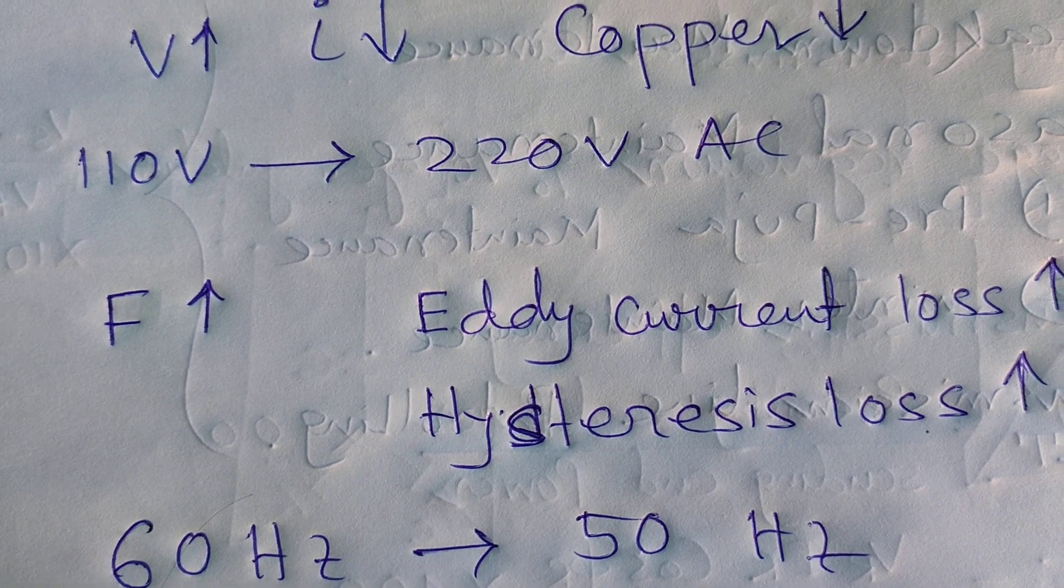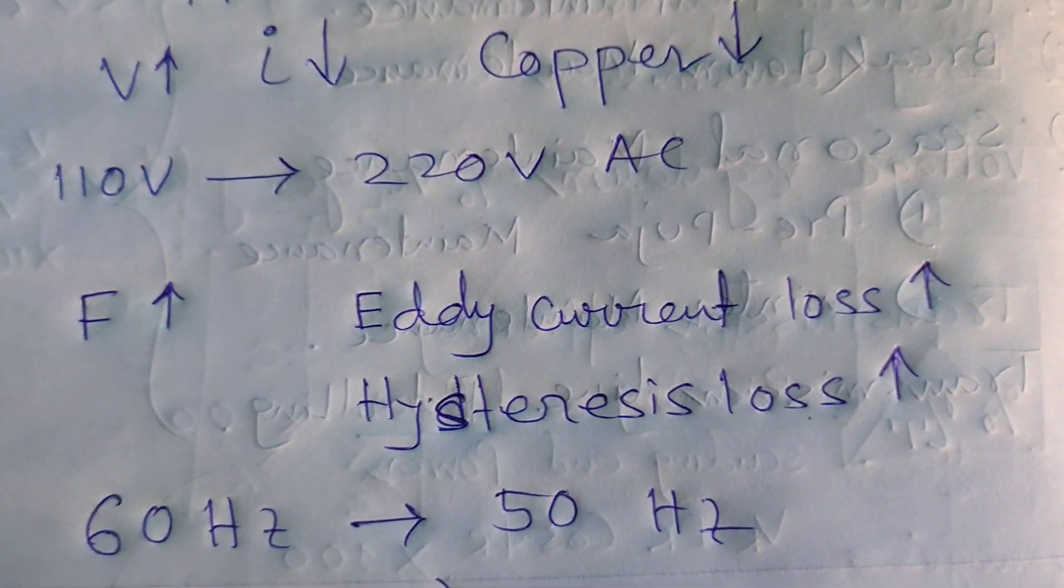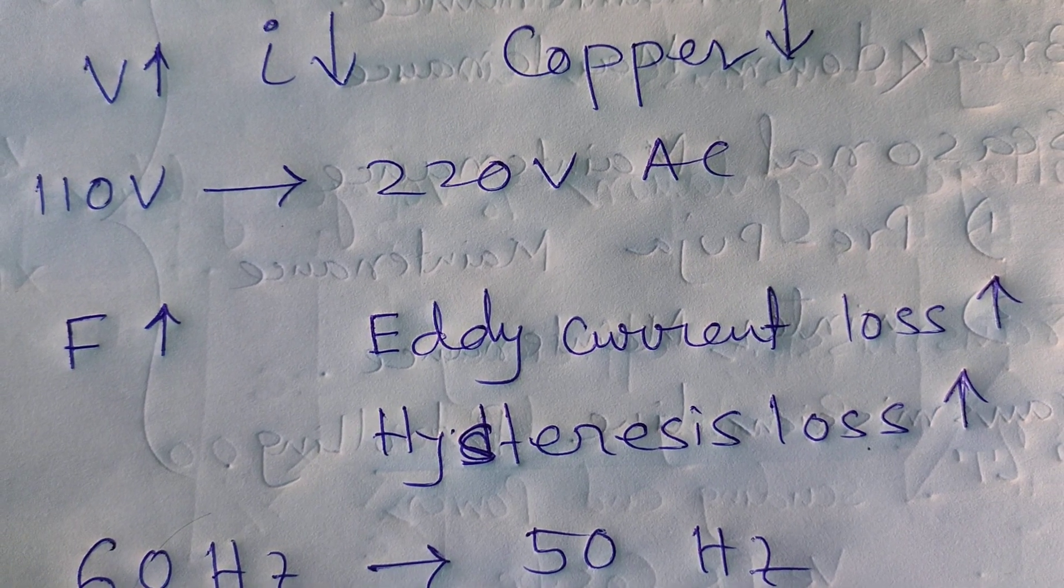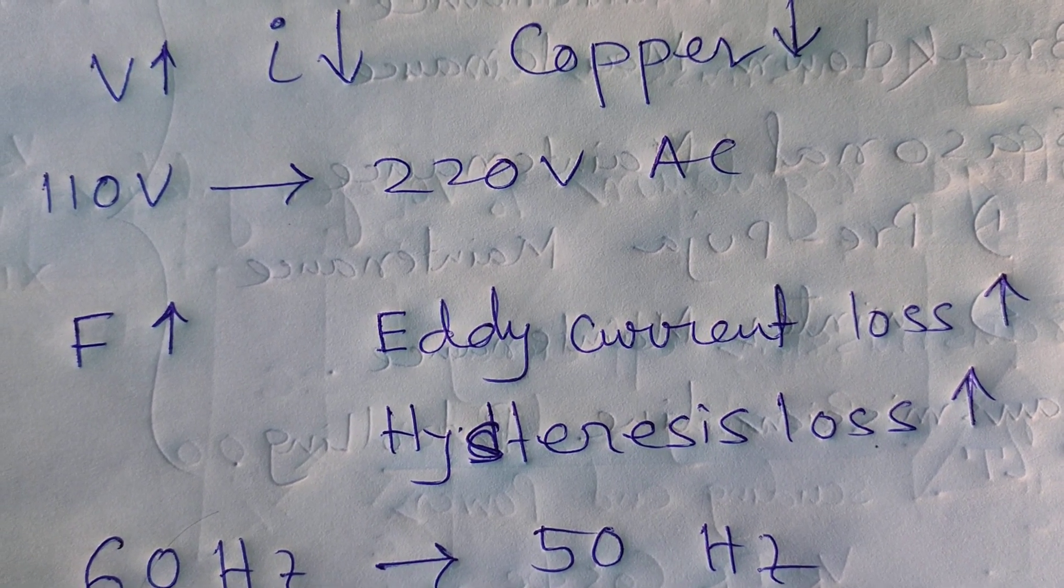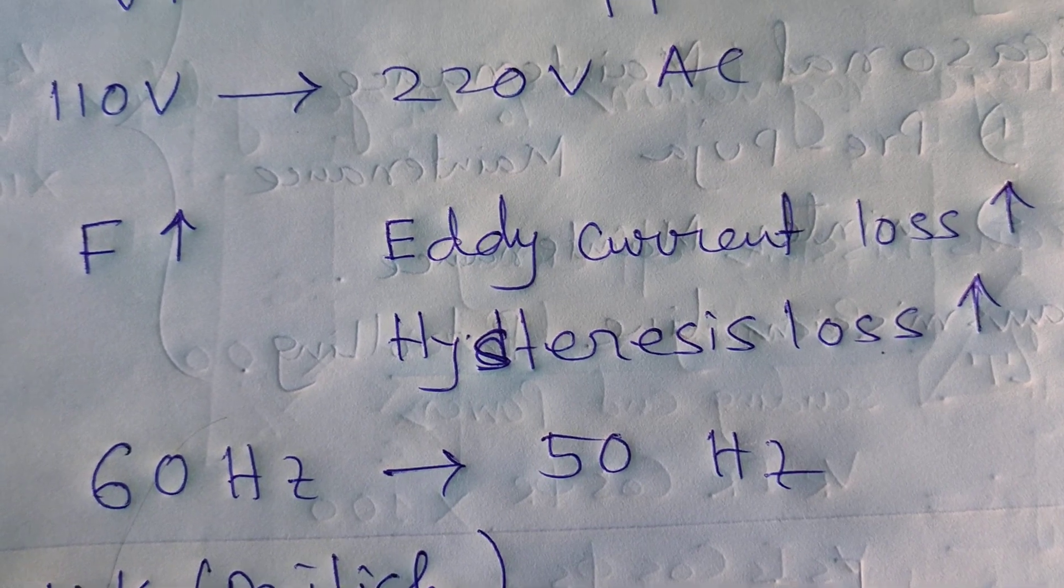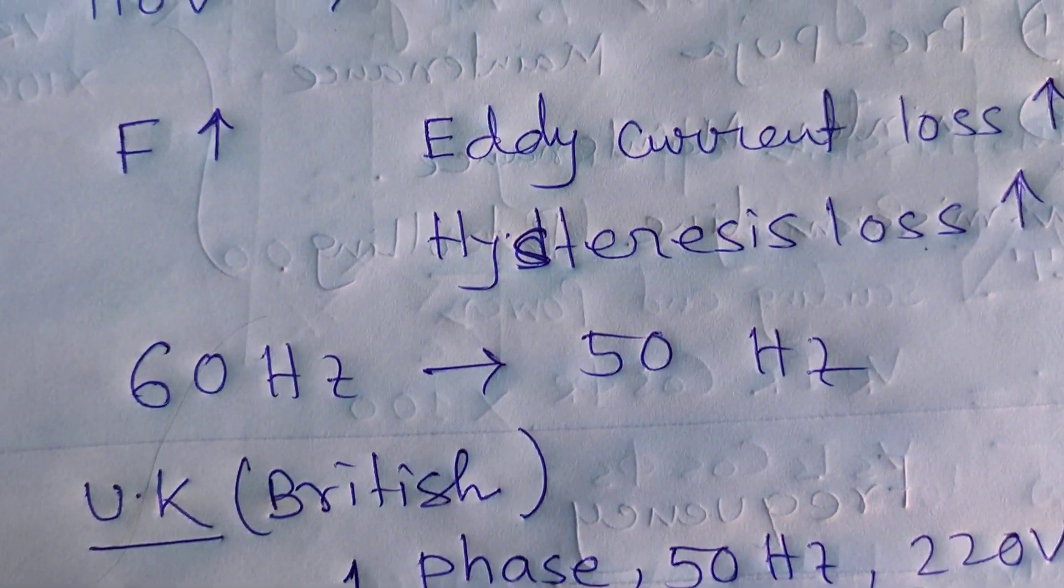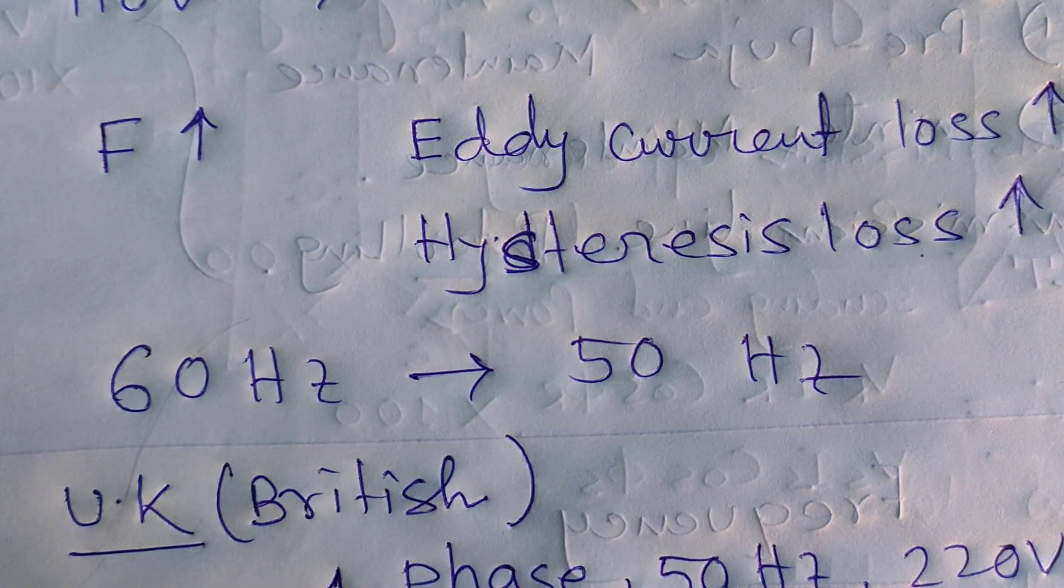If the frequency increases, the eddy current loss and hysteresis loss will increase. So depending on this basic principle, they decreased the frequency from 60 Hertz to 50 Hertz.